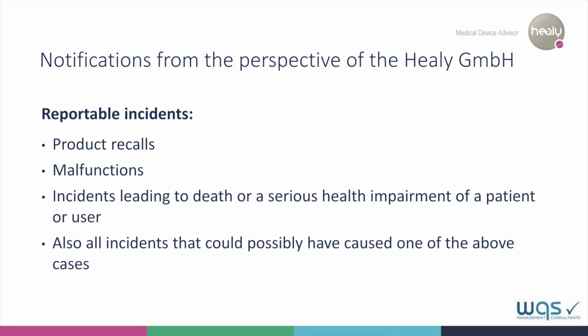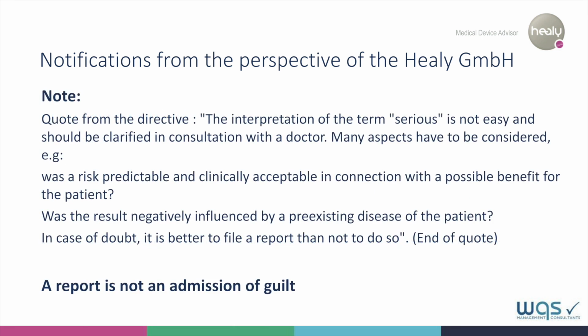As a manufacturer, we must comply with our reporting obligations in the following cases. In the event of product recalls or malfunctions attributable to product defects. In serious cases, such as a serious health impairment or even death of a user. Also for all incidents that could possibly cause one of the above cases. If the term serious cannot be exactly clarified by the manufacturer, the decision should be made to file a report. Note, a report is not an admission of guilt.